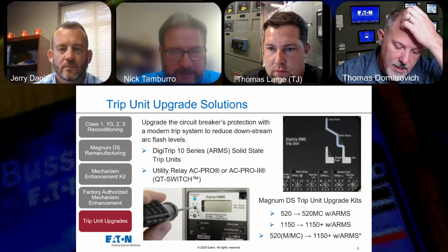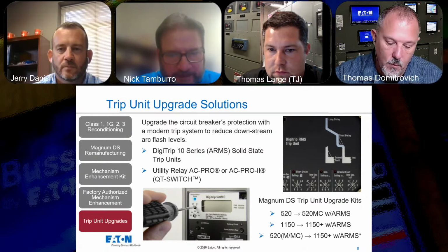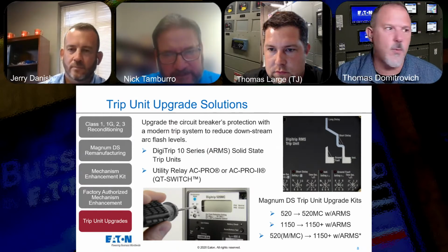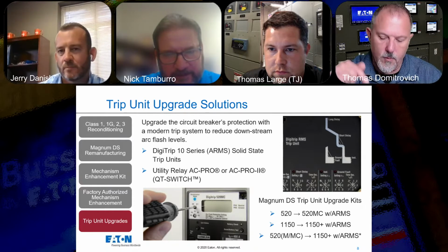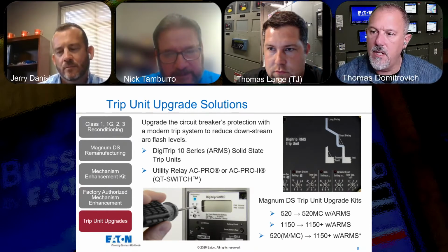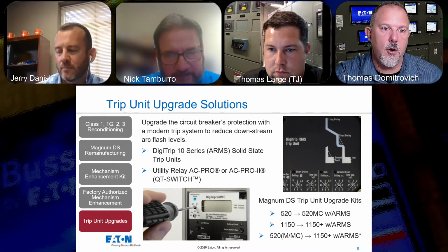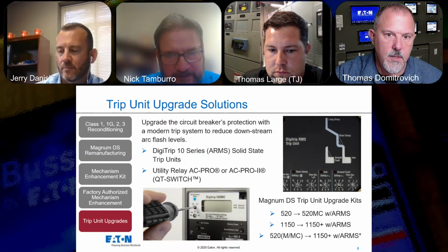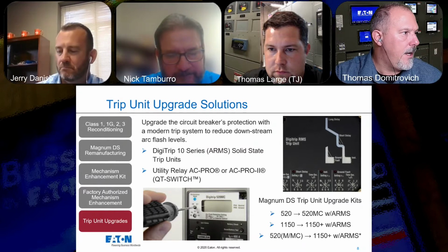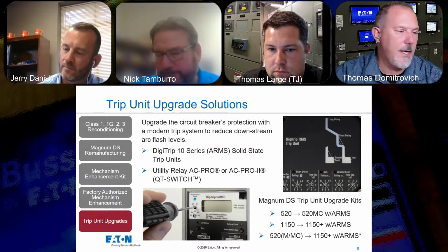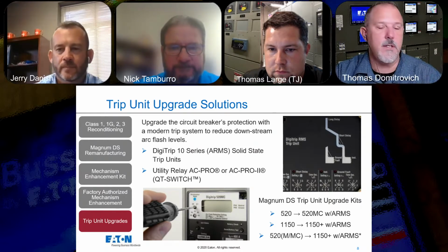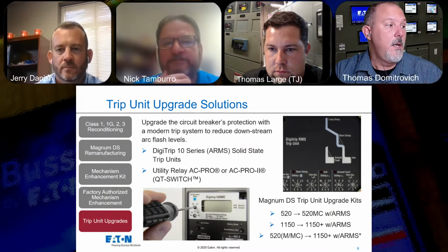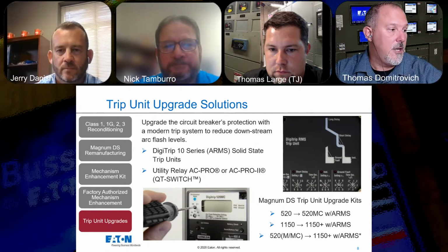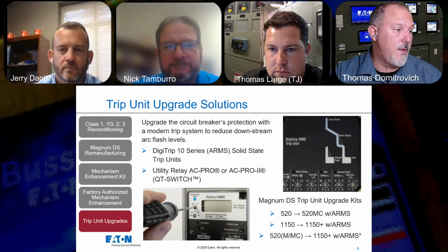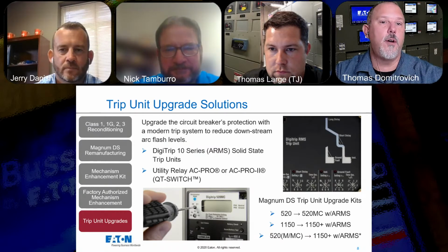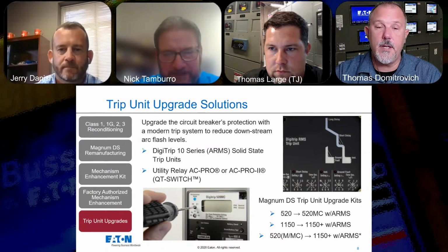And it has to be listed, because there was a change in Article 240. It's in the 2023 code cycle. We're going to require in Article 240 for the trip unit to be listed for installation on the breaker. That is a 2023 code cycle change. I'd have to find that exact section to get the exact language, but we're talking about it on Code Panel 10 to address the listing and testing of those trip units, because I think there are some people out there that want to just put anybody's trip unit on any circuit breaker, and that would be a technical term, ungood.